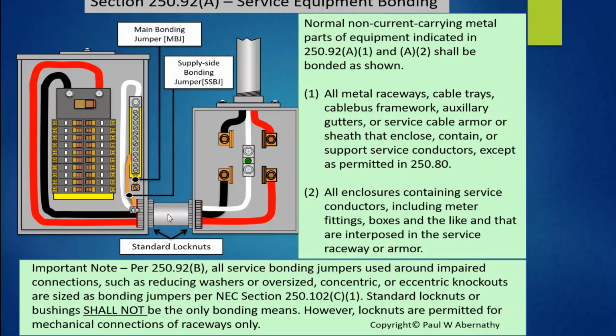Now you get to this raceway. In this case, let's say it's just the nipple. Now you're required to bond this raceway. Whether you do it on this side or on this side is irrelevant. I have to bond it on either side. So in this case, I'm bonding it in the service equipment panel. Here's the supply side bonding jumper, and it connects over to the grounded conductor here. This is sized based on the service entrance conductors that are feeding this service equipment. That's what it's based on. We've already done that. We know how to size it.